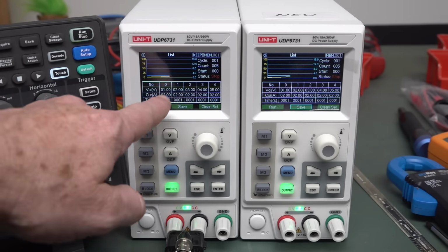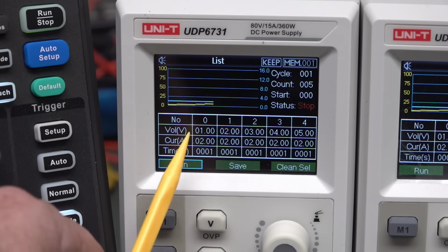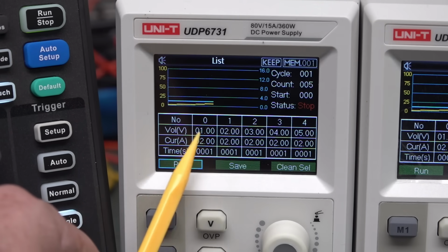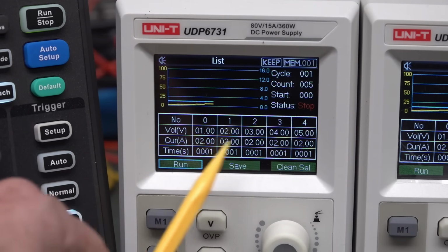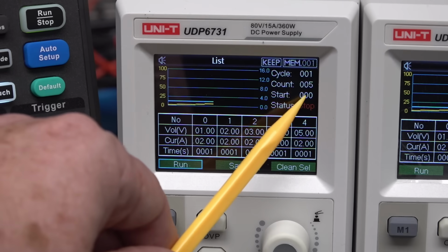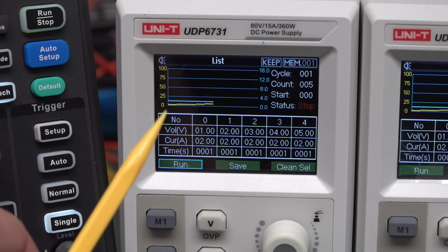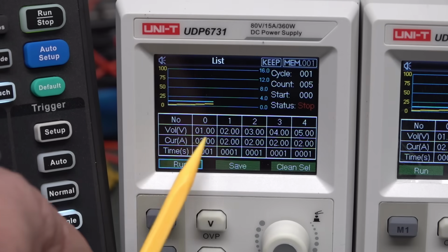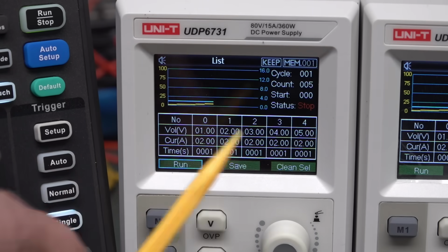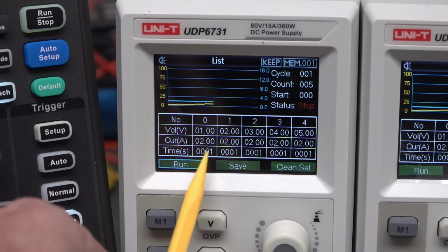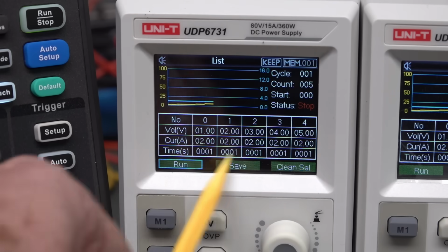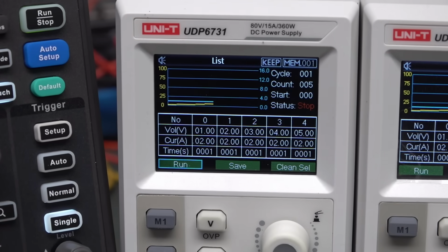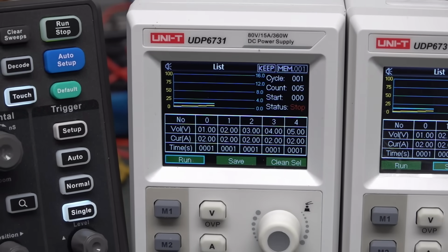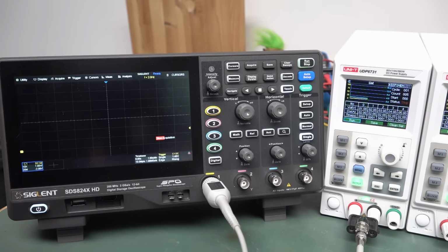And in that video I just programmed in a simple 1 volt step. So 1 volt, 2 volts, 3 volts, 4 volts, 5 volts, so 5 counts total, and it cycles through one time, so it just does those five steps one time, and there's 1 second delay between each one. Current limit doesn't matter. I just set it to like 2 amps, and we had a problem with it. So let's see if we can recreate that now.